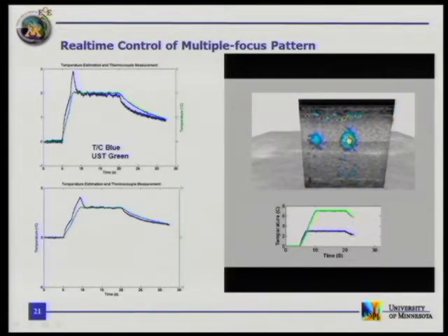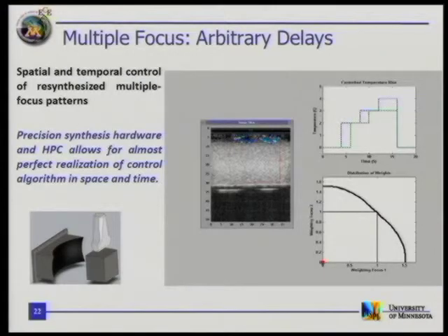On the left, you see the thermocouple measurement in blue, and the ultrasound thermography measurement in green. What's this? For the experienced hyperthermia folks, Bob McGuff, you're still here. Thermocouple artifact. Okay? That's because after we reached the set point on the first one, we increased the power, so you can see that thermocouple self-heating artifact right away. So it's exciting for us that we can do this. We can actually get even less artifact in the non-invasive data. So this is the future, I hope, of surgery.